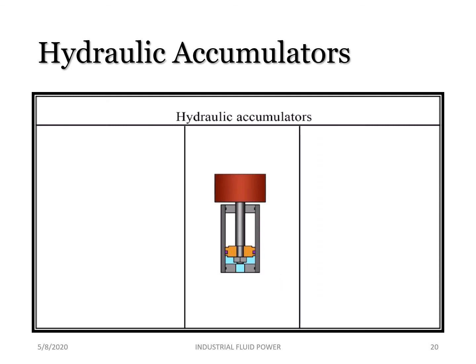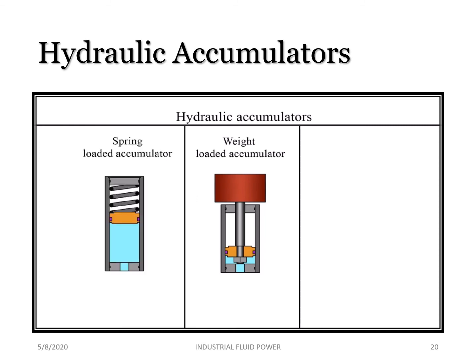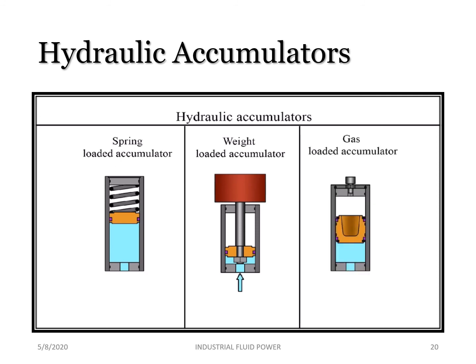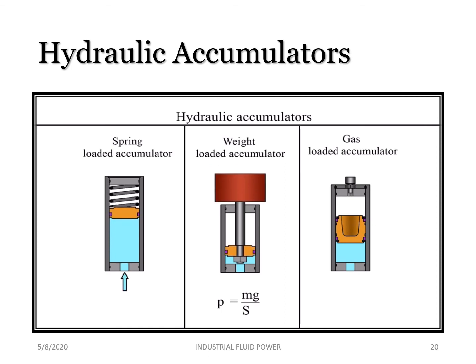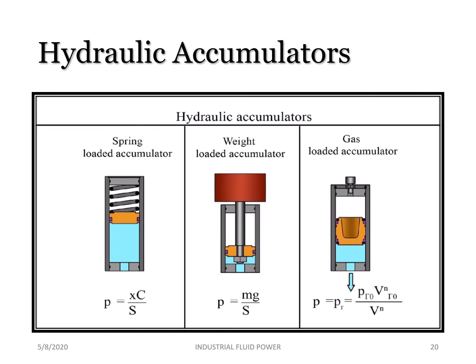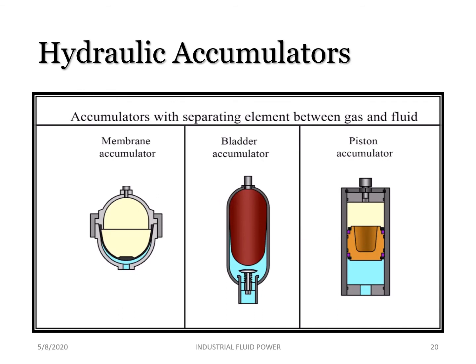There are three types of accumulators used in hydraulic systems: weight loaded, spring loaded, and gas loaded (hydro-pneumatic) accumulators. A balance is maintained between the pressure in the fluid and the opposing pressure produced by the weight, spring, or pressure created from the gas. The following types of accumulators with separating elements are used in industry: piston, membrane, balloon, or bladder accumulators — they differ in the way gas and liquid are separated.